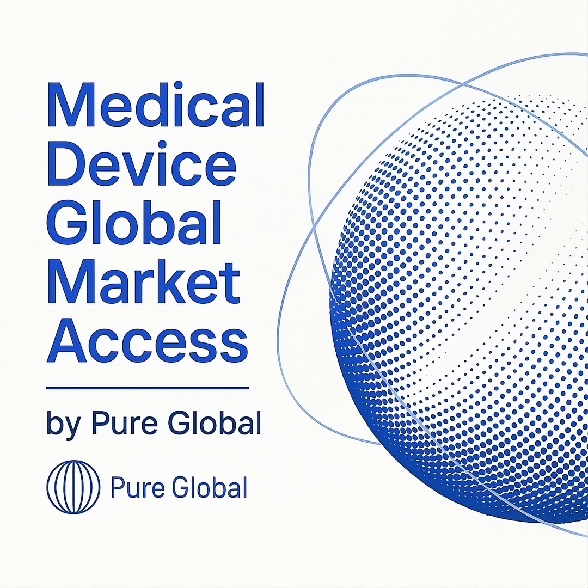Once submitted, the Center for Medical Device Evaluation reviews the dossier, a process that can take anywhere from 16 to over 26 months for Class 2 and 3 devices. The NMPA registration certificate, once issued, is valid for 5 years, after which you must apply for renewal. This entire process demands meticulous preparation and local expertise.